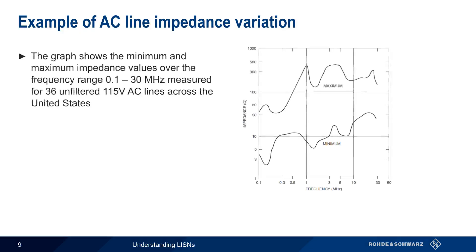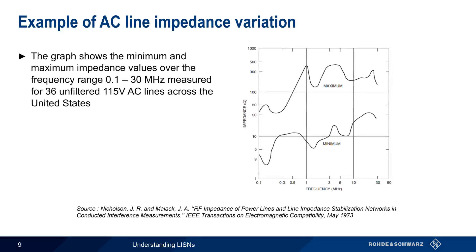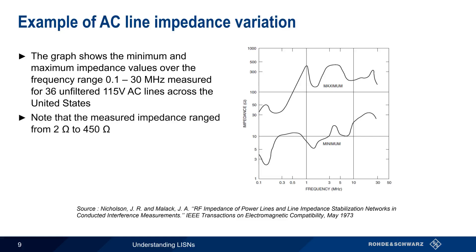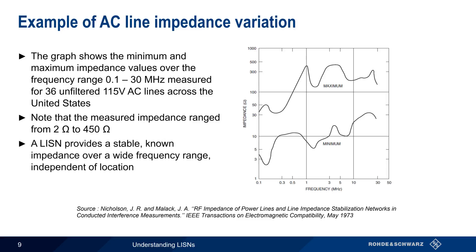If you're wondering how much the impedance of an AC outlet varies from place to place, this graph shows the maximum and minimum impedance values at 36 unfiltered outlets across the United States. Note that the impedance varied from a minimum of about 2 ohms to over 450 ohms over the frequency range used for most conducted emissions testing. This shows why a LISN is helpful in ensuring that a stable, known impedance is present regardless of location.